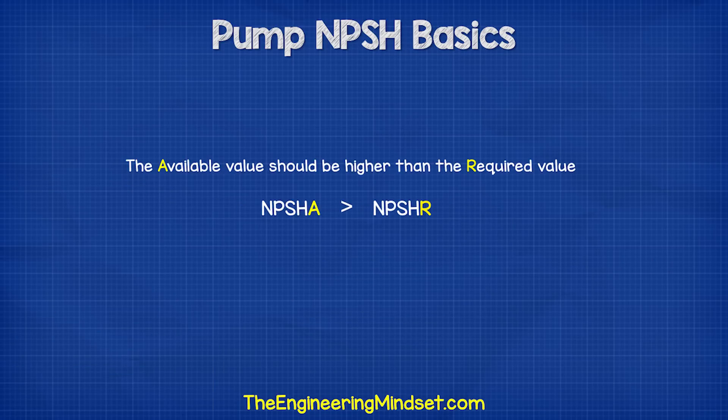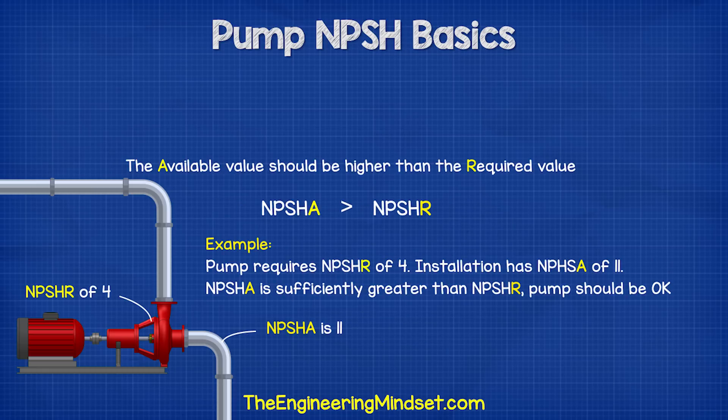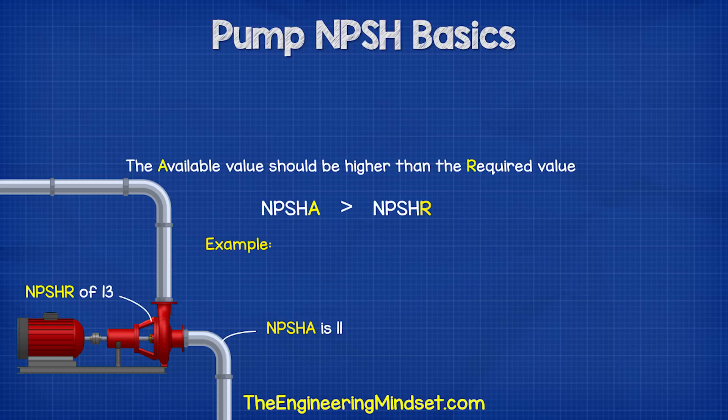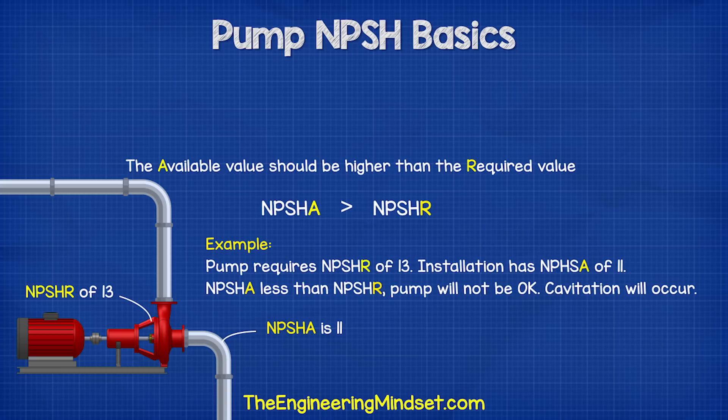The available pressure should always be higher than the required value. For example, if we have an installation and we calculate the NPSH-A as 11, but the pump requires an NPSH-R of 4, then the pump should be okay. However, if we installed a pump that required an NPSH-R of 13, then the available NPSH is insufficient and cavitation will occur.